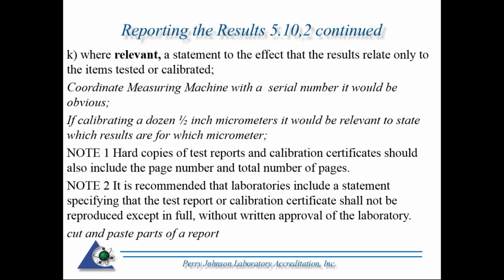Couple recommendations here. These are notes right out of 17025 at the conclusion of 510.2 Common Elements. Hard copies of test and calibration certificates should also include the page number and total number of pages. Previously we specified you have to indicate the end of the report. It's recommended that you include the page number and the total number of pages.